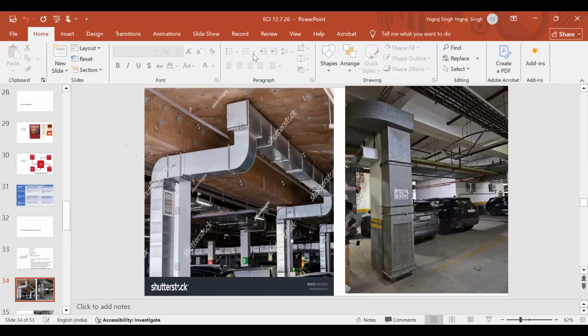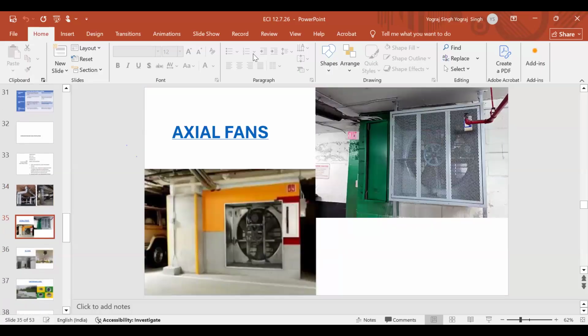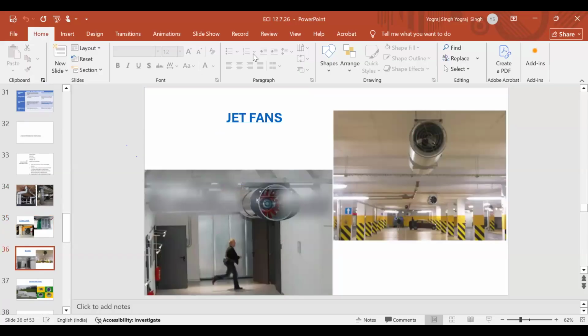So now, as in the case of a desert cooler, this air is being thrown away from the building through these large axial fans. It's something called jet fans. You cannot provide ducting to large areas, so you provide jet fans. You must have seen these days a lot of tunnels are being made by the highway authority. In tunnels, such fans are there, so they will channelize air through this, and so it will not require ducting. So cost saving will be there.